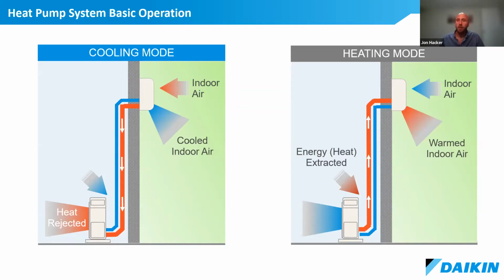A heat pump works pretty much under the same principles, but in reverse. So instead of capturing heat from inside and moving it outside, we're actually capturing heat from the outside, even when it's cold out. And it's hard to imagine, but at 0F or -10F, there's an abundance of heat to be captured in that air. The heat pump is going to capture that heat, move it inside via those refrigerant connections, and reject that heat into the space to maintain comfort.